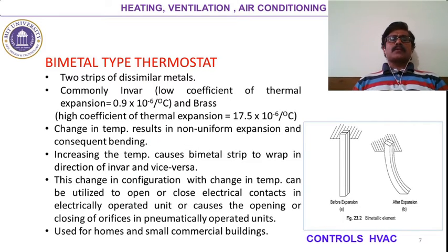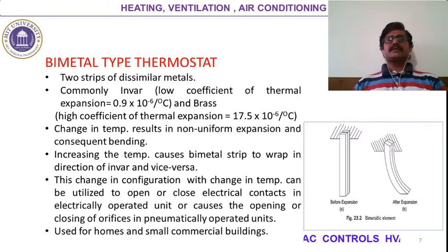Now this change in the configuration, meaning the change in the direction of bending of this bimetal strip with the change in temperature, can be utilized for further action. Further action means either to open or close the electrical circuit in contact with the electrically operated unit, or to cause the opening and closing of the orifices if your system is pneumatically operated.